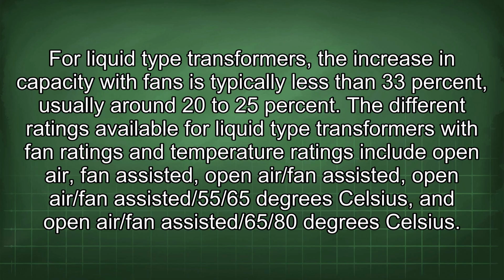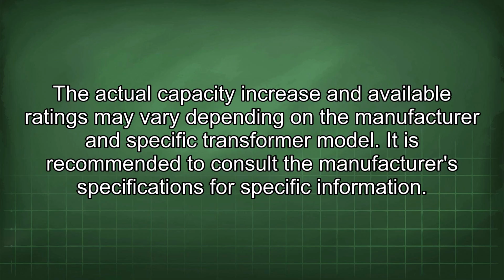For liquid-type transformers, the increase in capacity with fans is typically less than 33%, usually around 20 to 25%. The different ratings available for liquid-type transformers with fan ratings and temperature ratings include open-air fan-assisted, open-air/fan-assisted, open-air/fan-assisted/55/65 degrees Celsius, and open-air/fan-assisted/65/80 degrees Celsius. The actual capacity increase and available ratings may vary depending on the manufacturer and specific transformer model. It is recommended to consult the manufacturer's specifications for specific information.